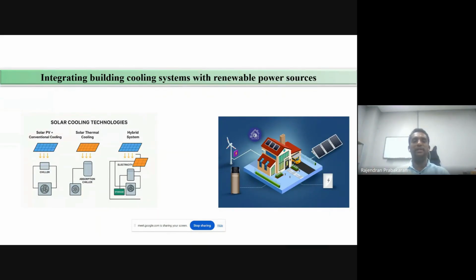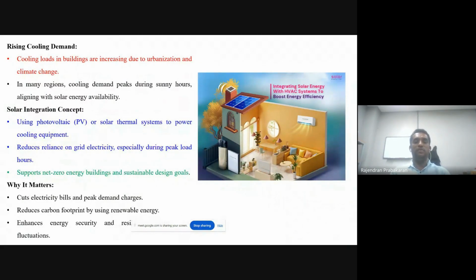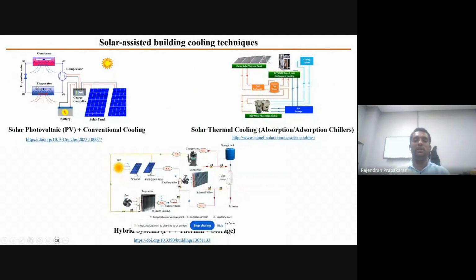There are 3 different kinds of cooling technologies already in use: solar photovoltaic plus conventional HVAC system, then solar thermal cooling plus absorption-based chiller systems, and third, hybrid solar PV and thermal cooling with HVAC systems. These are the 3 common categories available. With this concept, we can support net zero building certifications, cut the electrical bill and peak demand charges, and overall reduce the carbon footprint of the system. These are the 3 schematic representations of PV plus conventional cooling, solar thermal plus absorption chiller, and hybrid systems that we can see.